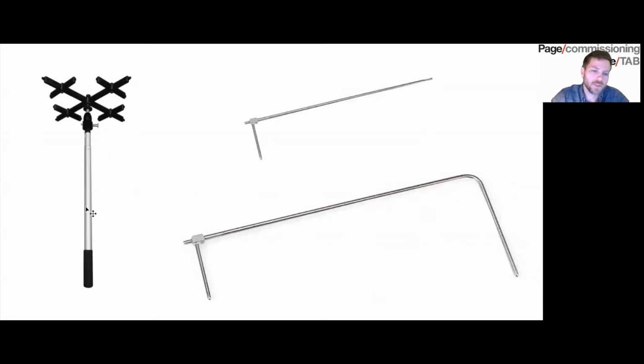Now, if some of you are wondering what a velgrid is, it's this device on the left. There are certain situations where this device can be accurate, but in quite a few situations it is not. So even though the manufacturer will state that this device is accurate, plus or minus 2%, there's so many situations where that is not true. And so it's better to use a pitot tube, which is this device down here, or an airfoil, which is this device here. And obviously these are used in the ductwork.